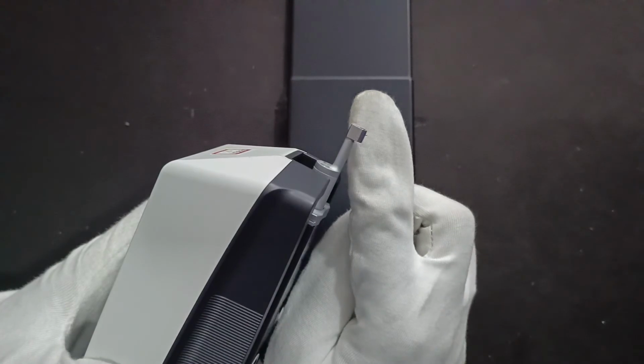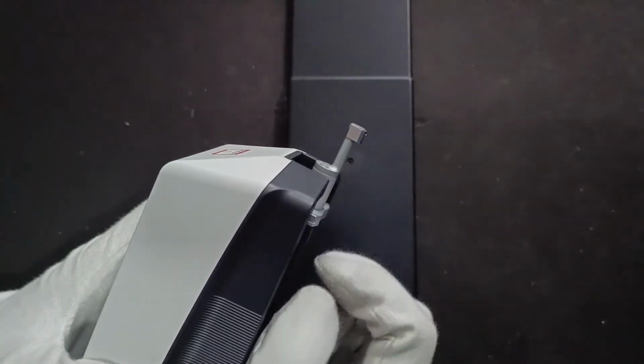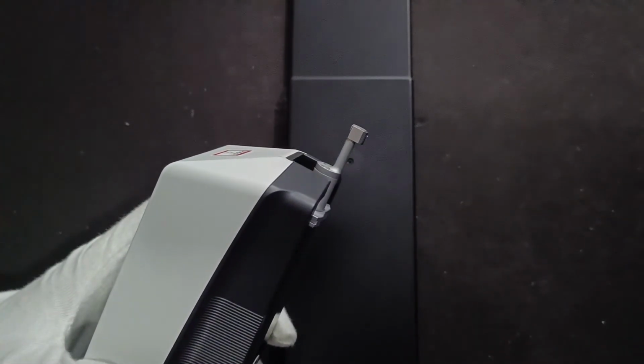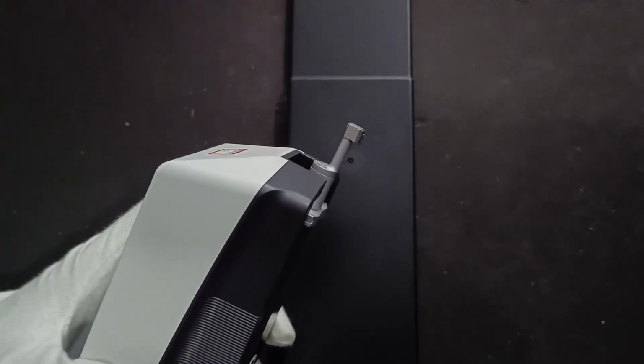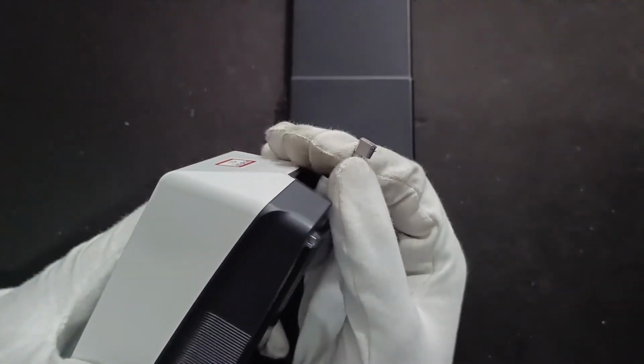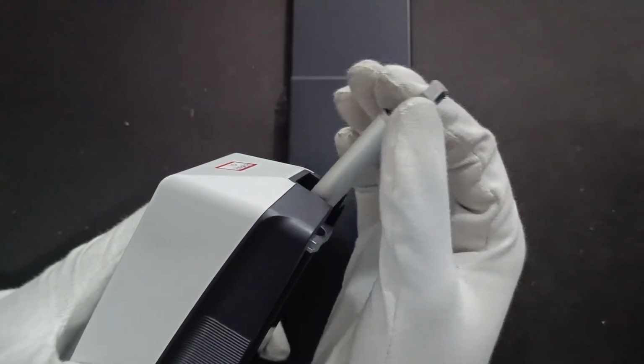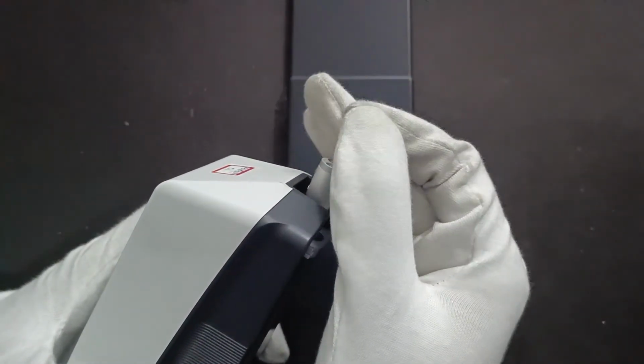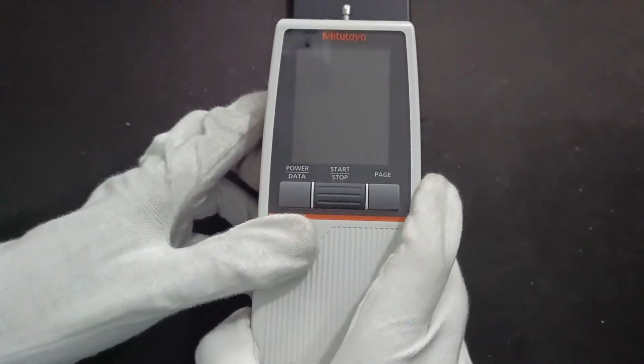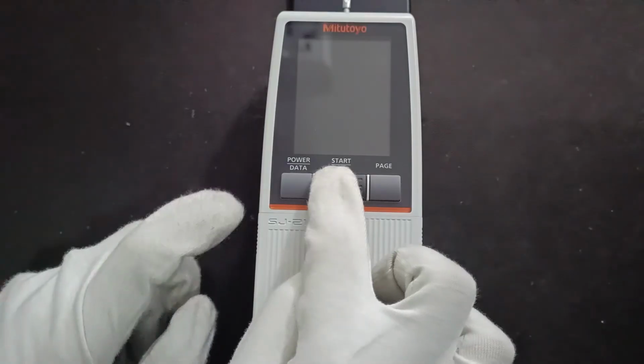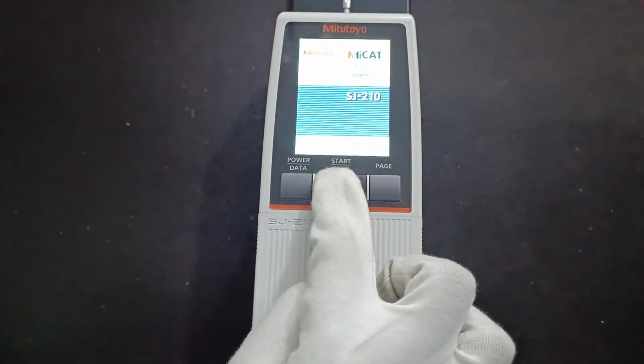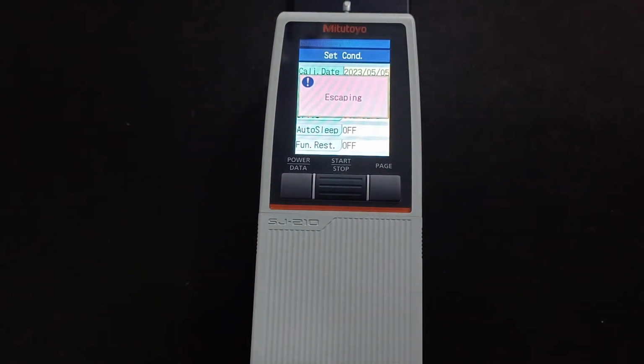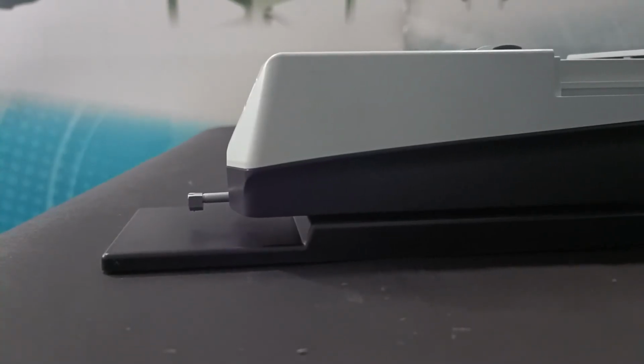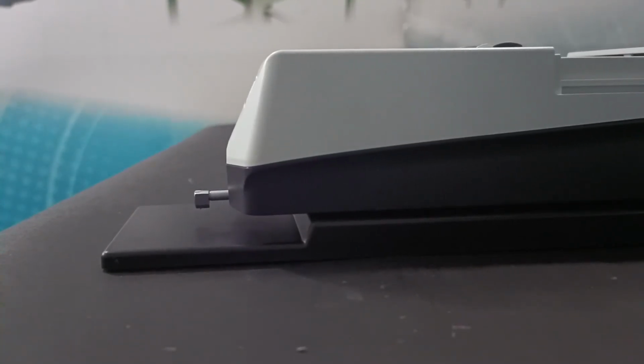The stylus of SJ-210 has an extremely delicate diamond tip of 5 micron radius, and ensure that the stylus is not in contact with any surface when not in use. While storing the instrument, remove the probe from the drive unit or use this function. After the instrument is turned off, long press and hold the start or stop button and press the power or data button. You would now see a message stating escaping on the screen and the probe will slowly move into the drive unit housing.